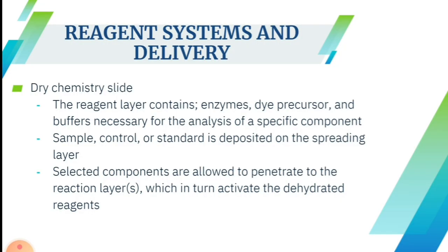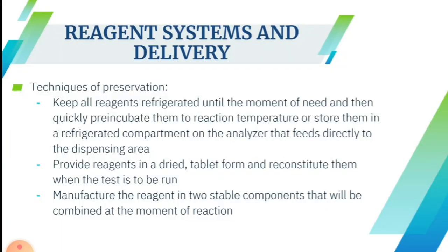So the reagent layer contains enzymes, dye precursors, and buffers necessary for the analysis of a specific component. The sample, control, or standard is deposited on the spreading layer. And then selected components are allowed to penetrate to the reaction layer, which in turn activate the dehydrated reagents. So we also have techniques of preservation. You should keep all reagents refrigerated until the moment of need and then quickly pre-incubate them to reaction temperature, or store them in a refrigerated compartment on the analyzer that feeds directly to the dispensing area.